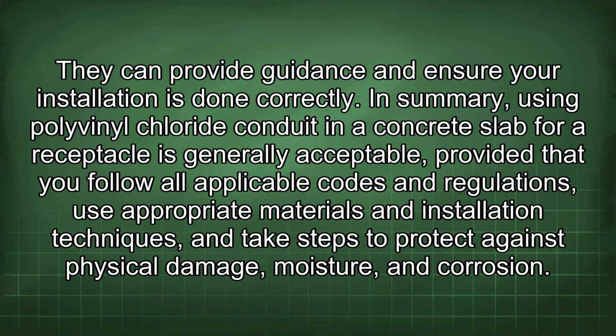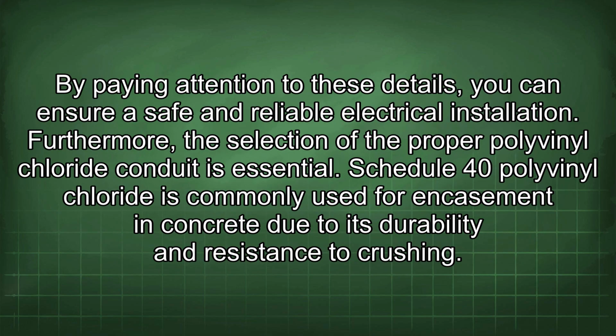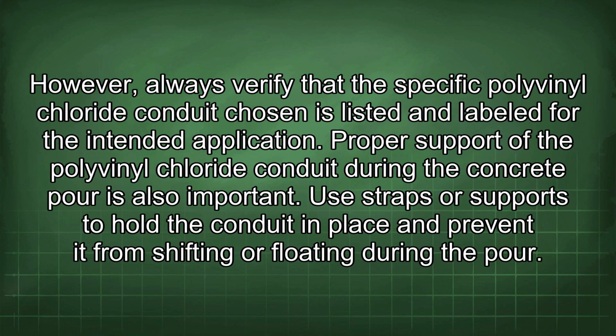In summary, using polyvinyl chloride conduit in a concrete slab for a receptacle is generally acceptable, provided that you follow all applicable codes and regulations, use appropriate materials and installation techniques, and take steps to protect against physical damage, moisture, and corrosion. By paying attention to these details, you can ensure safe and reliable electrical installation. Furthermore, the selection of the proper polyvinyl chloride conduit is essential. Schedule 40 polyvinyl chloride is commonly used for encasement in concrete due to its durability and resistance to crushing. However, always verify that the specific polyvinyl chloride conduit chosen is listed and labeled for the intended application.